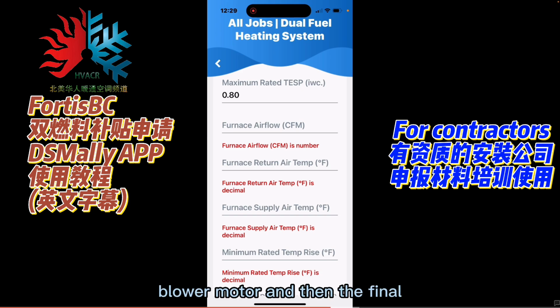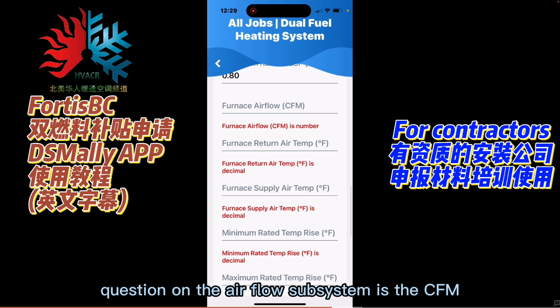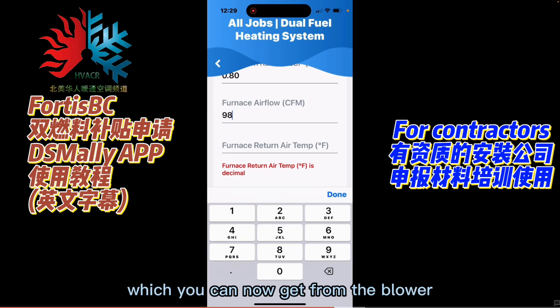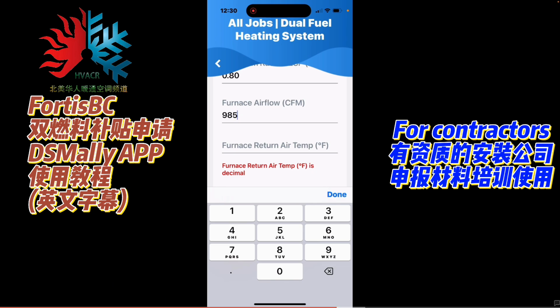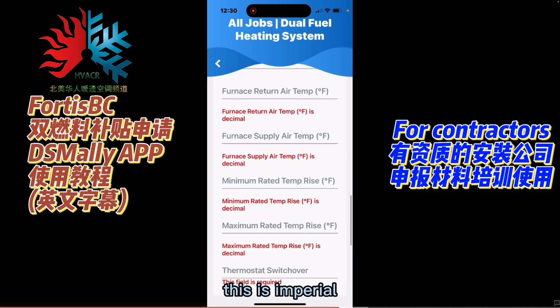Blower motor. And then the final question on the airflow subsystem is the CFM, okay, which you can now get from the blower tables because you have the measured total external static pressure. Now we get into temperatures, the measured return air temperature. This is imperial.